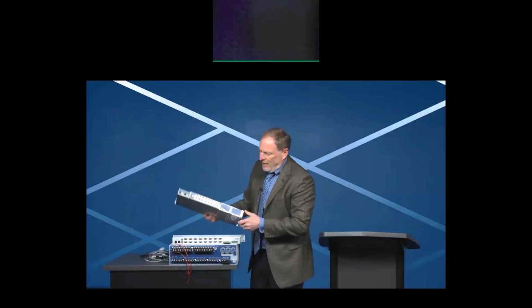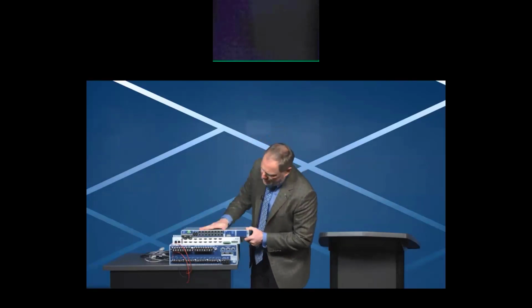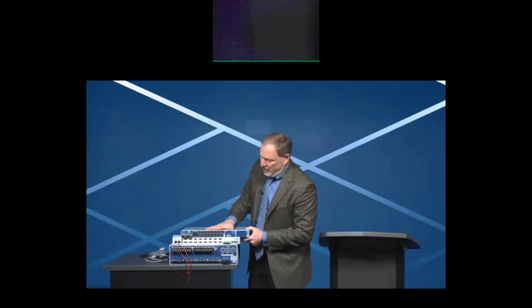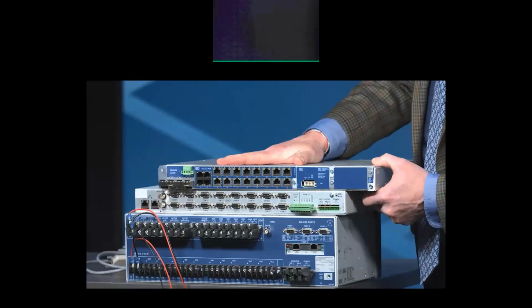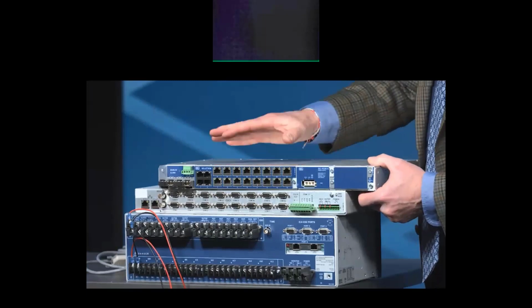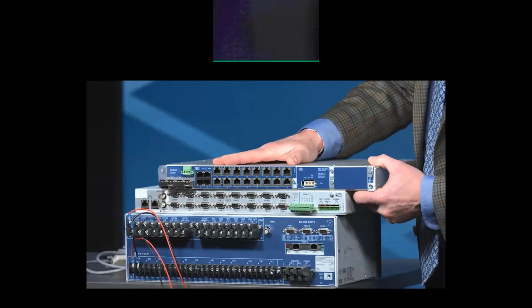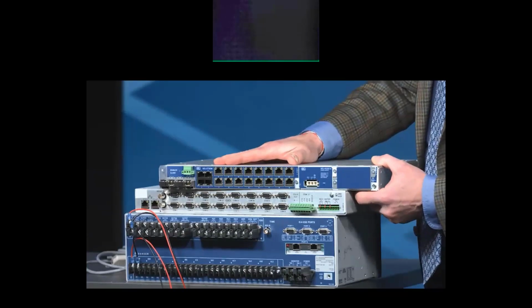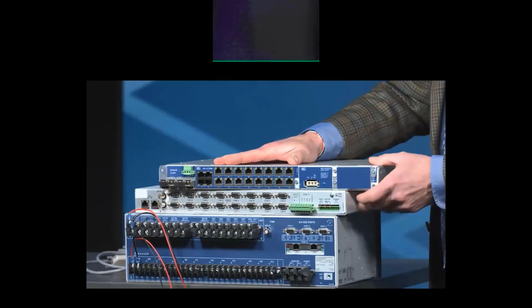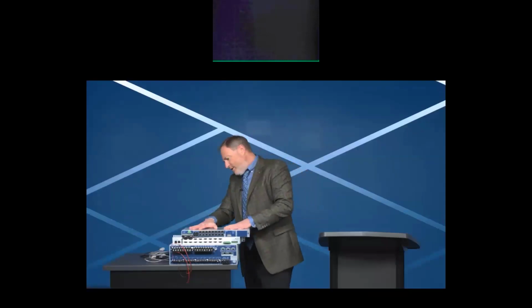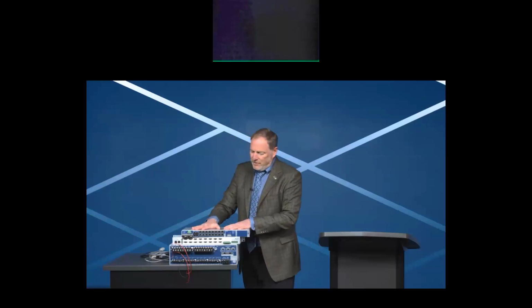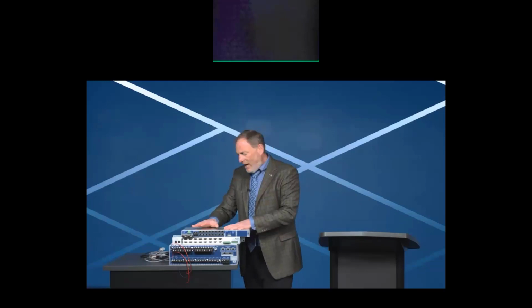Here's the SEL Ethernet switch. This version has a radiator to dissipate heat, and all the Ethernet connections you might see on an IT switch on the back, but it is very different. It is designed for the OT environment. It's designed and built like a relay, no moving parts, doesn't rely on fans, and it's expected to work 24/7 for 25 to 30 years. Now, from field service information, we know that this particular Ethernet switch has an MTBF of 430 years.